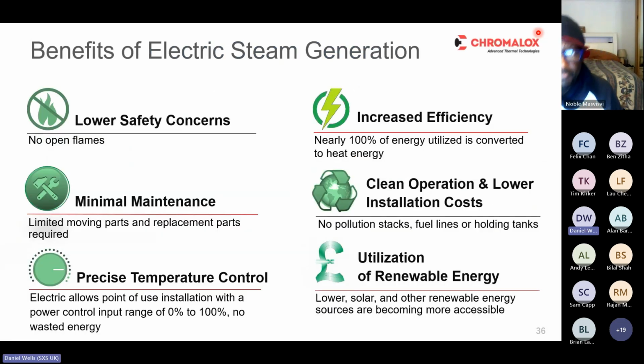Electric steam generators, standalone electric boilers or electric steam generators, are very, very efficient, very reliable. They can get up to temperature quickly and reliably, very, very attractive. And this is what our sister company Chromalox produces. I think one of the drawbacks with an electric boiler is it needs to be sized in accordance with that maximum instantaneous peak demand for energy at 9 o'clock on a Monday morning. So in many cases, it's going to need to be significantly oversized to accommodate that peak load compared to the base load, for the simple reason that electric steam boilers can't respond as quickly as gas boilers, and they don't contain the same thermal energy in storage as a traditional gas boiler.